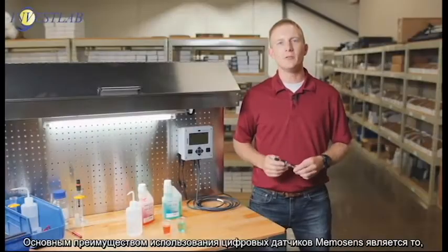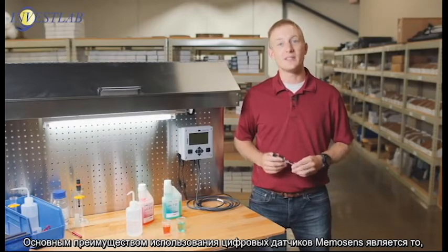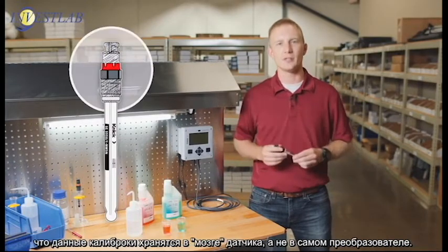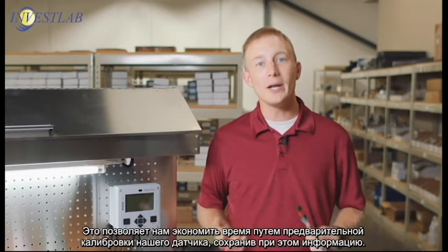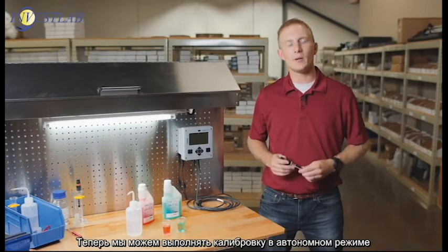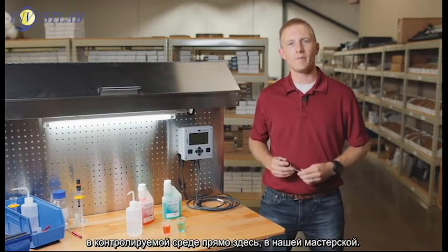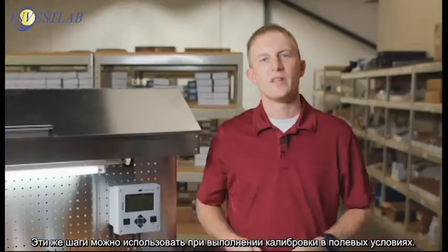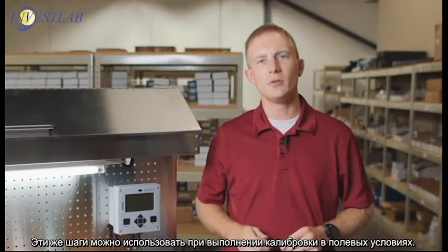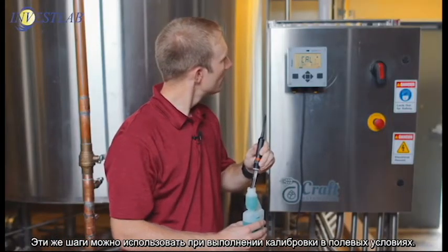The main benefit of using Memosens digital sensors is that the calibration data is stored in the sensor head and not in the transmitter. This allows us to save time by pre-calibrating our sensors and storing them on the shelf. We can now perform our calibrations offline in a controlled environment right here in our workshop. These same steps, however, can be utilized when performing a calibration in the field.